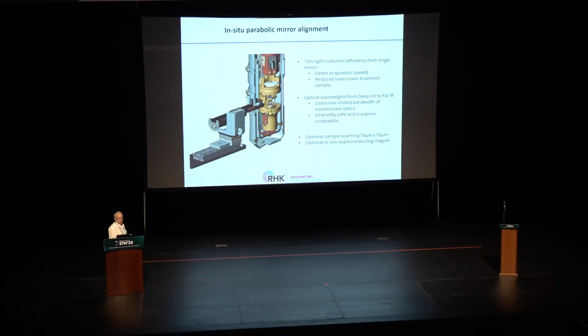And the reflective optics are inherently cryogenic and UHV friendly. They don't outgas. You can bake them, which is not something that's the same. Putting transmissive optics into vacuum degrade over time. One new feature that we're putting on that one of our customers had requested: generally the first people wanted to scan really atomic scale, but on some of the near field optics where you're scanning larger, scanning the sample, so we'll be able to scan the probe at high resolution and then the sample at plus or minus 15 micron at low temperature.